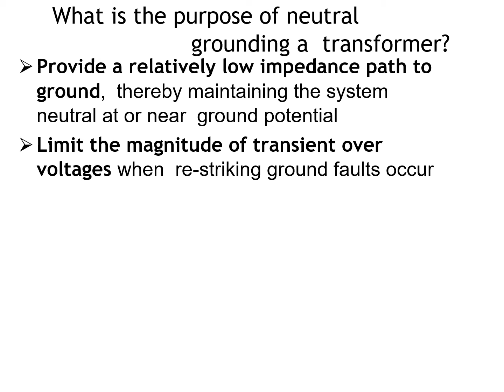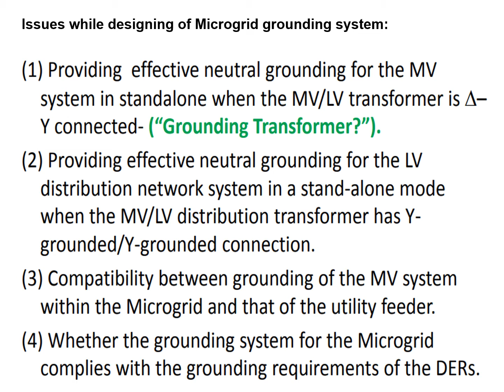First, the main method to provide an effectual neutral grounding for this medium voltage system in standalone mode when this MV or LV transformer is delta star connected. Second, the method to provide an effectual neutral grounding for the LV distribution network system in standalone mode when this MV or LV distribution transformer is star grounded. Third, the method to maintain compatibility within the microgrid and between the utility feeder supplying the microgrid and grounding of the MV system. And the last one, whether the grounding system fulfills the grounding necessities of the existing distributed energy resources installations.